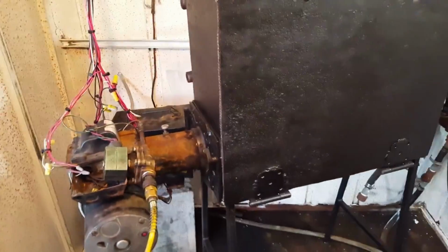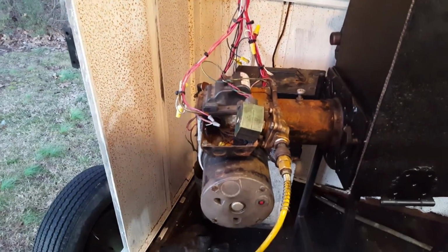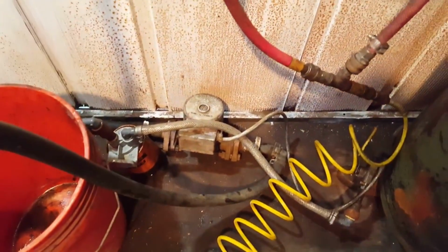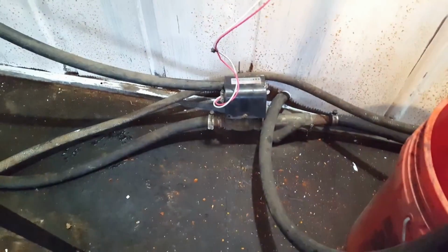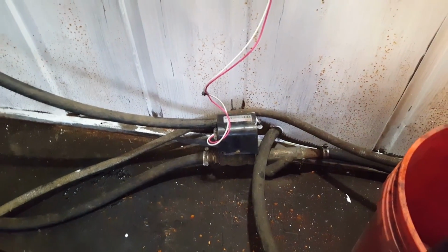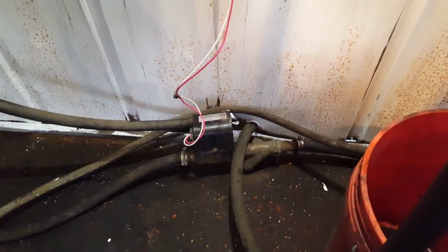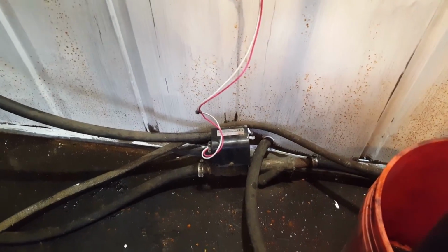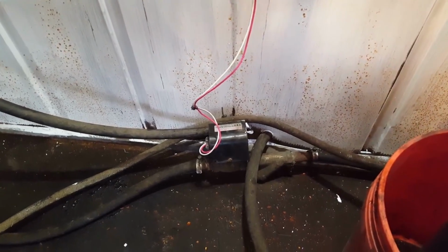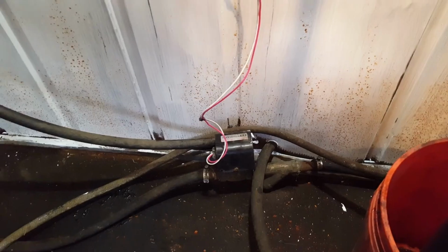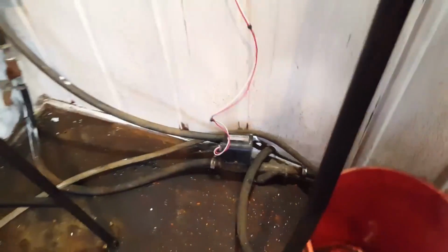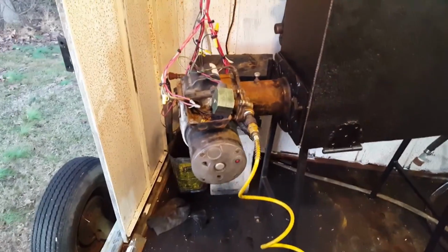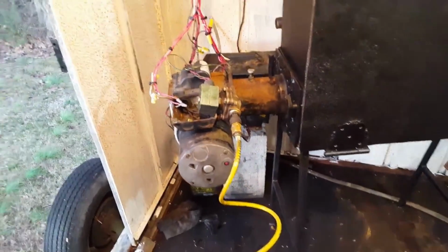Okay, once it gets called for heat and turns all these valves and everything on, it'll also turn the circulating pump on, which will turn the flow sensor on. If the flow sensor isn't sending a signal to the PLC, it'll shut it down. But I give it like 3 to 5 seconds for it to get the water flowing before it'll shut it down. If all of that is satisfied, then this thing should start and keep on running until the thermostat's satisfied, it'll lose that input on the PLC and it'll shut it down.